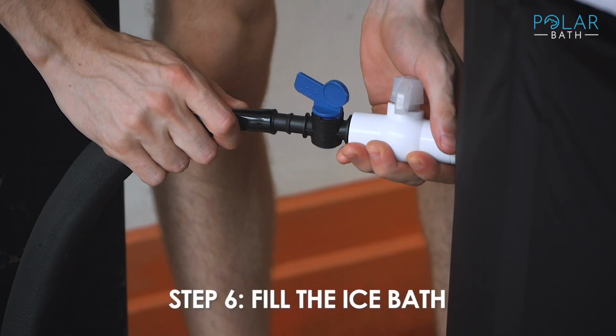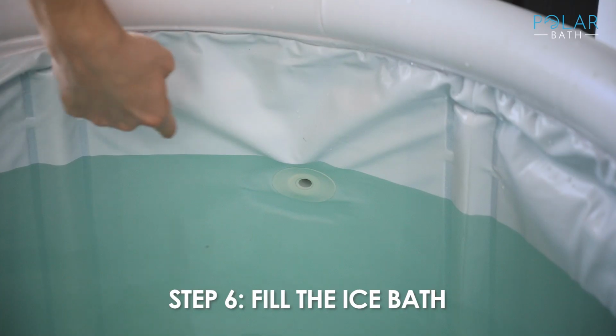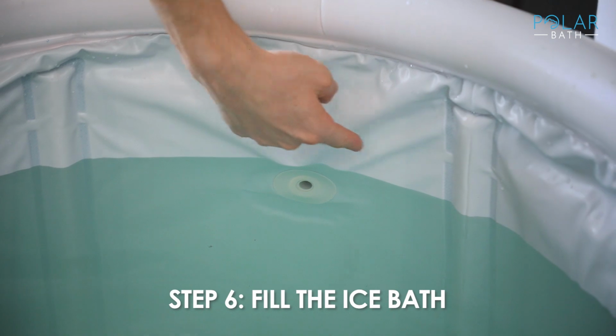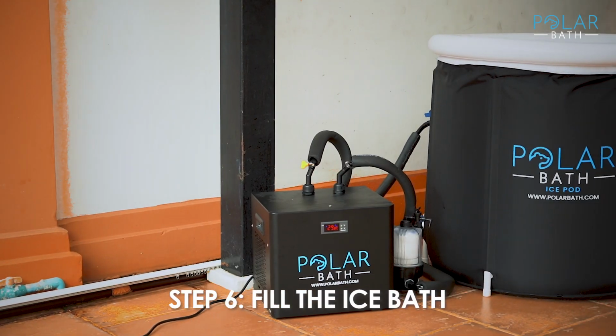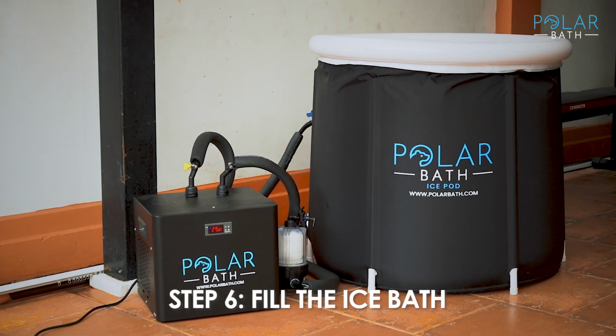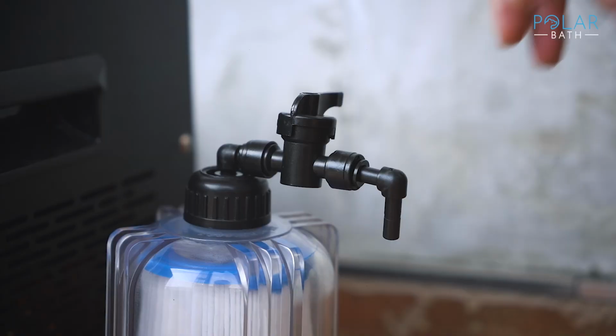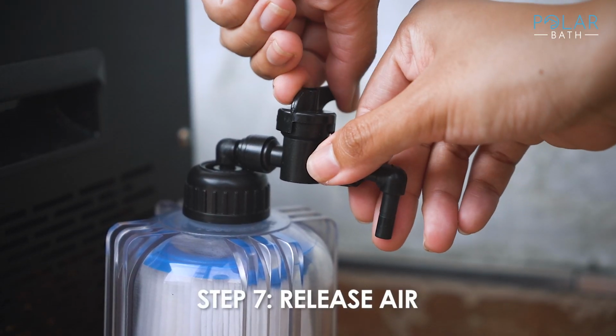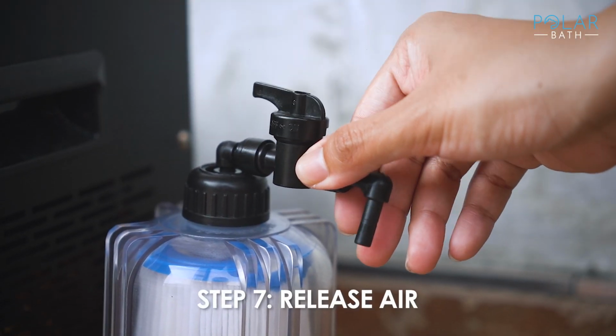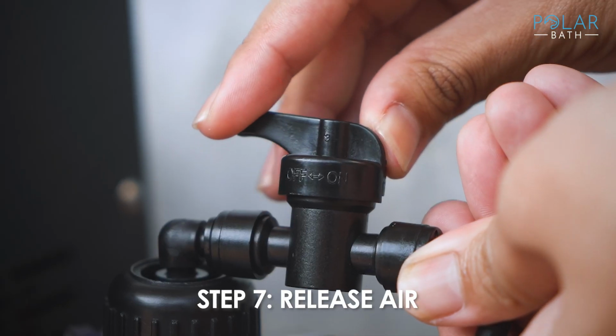Before filling your ice bath, make sure the valves are closed. Then, fill it with water, ensuring the water level is above the filter in the chiller. Check all connections for any leaks and use the Teflon tape if needed. Now it's time to release the air from the system. Open the air release valve on the filter to let the air out. Once water is flowing, close the valve.